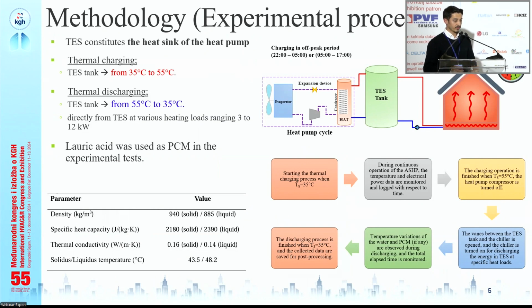The thermal energy storage unit constitutes the heat sink of the heat pump, and therefore in the thermal charging process, we heat up the water inside the thermal energy storage tank using the air source heat pump from 35 degrees Celsius initially to 55 degrees Celsius. Once 55 degrees Celsius is reached, the thermal charging operation is terminated, and then thermal discharging is immediately started from 55 degrees Celsius to 35 degrees Celsius. In the experimental conditions, we have taken into account different heating loads ranging from 3 to 12 kilowatts.